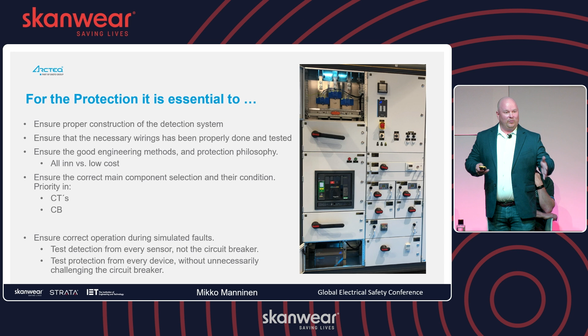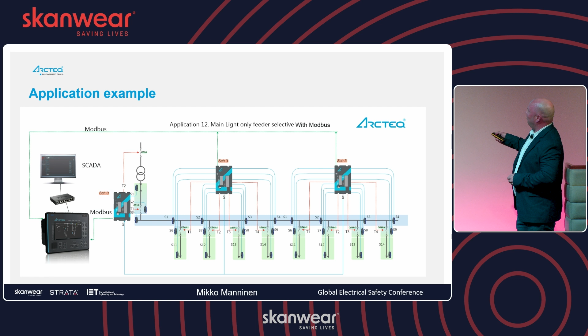And here is just an example. This is a feeder selective example. Sorry, I will turn a little bit. So there is, for example, this feeder selective point sensor in each cubicle, in each closed compartment. For example, here, cable termination, circuit breaker, and a bus bar. Feeder selective means that if you have a fault in this cable, the intention is to trip only that breaker. And if you have the fault above, you trip the main breaker and upstream.